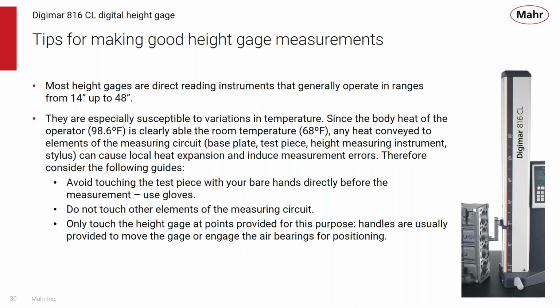Use the knobs and the handles that are on the gauge to position it. So that's what you want to do. You want to touch the height gauge at the points provided for the purpose. The handles and the air-bearing movement switches are what you want to move the gauge with, and that will not transfer heat to the measuring circuit.